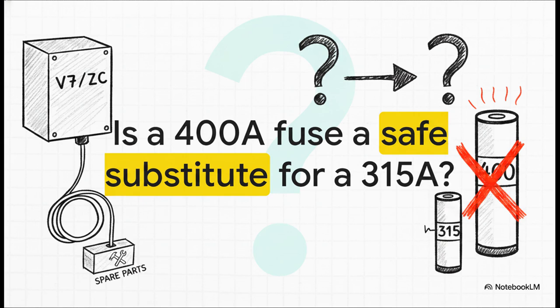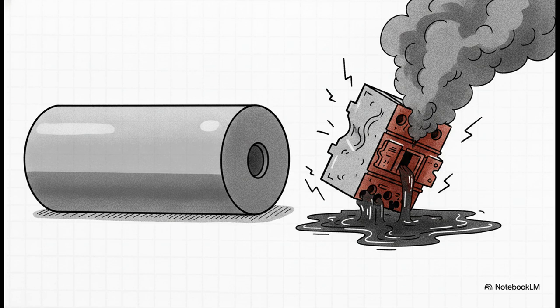So let's do a quick check for the engineers out there. Say a spare parts order arrives on the deck plates for your V7/ZC unit, but they sent a 400 amp fuse instead of the specified 315 amp fuse. Is this a safe substitute? Absolutely not. You should never substitute fuse ratings in this system. Swapping to a larger 400 amp fuse completely removes that critical safety margin. It breaks the deliberate coordination scheme that protects the contactor during a fault. If you were to install that 400 amp fuse, your contactor might actually melt down before the fuse even thinks about blowing.